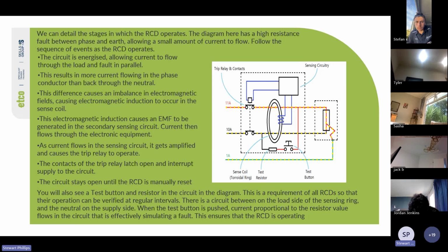Pretty much all of your RCDs or RCCBs will be manual reset. And even your MCBs, if you hold the MCB, like you see so many people take photos of MCBs not being able to activate because they've wound some copper wire and attached it to a screw. Internally, your circuit breaker will still activate. Even if the switch is held shut, the circuit breaker will still activate. It's just that the switch won't move. As soon as you let go of that switch, it'll flick down.